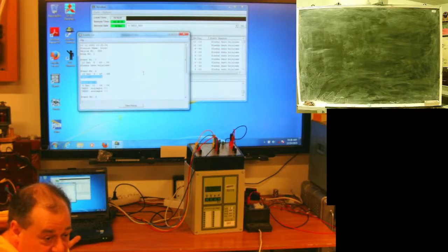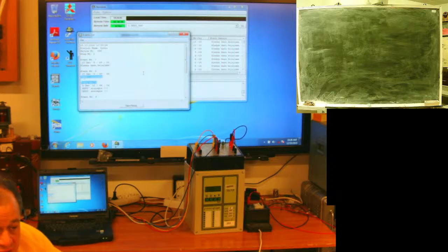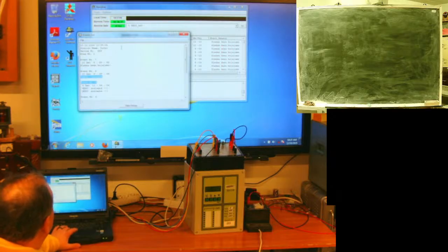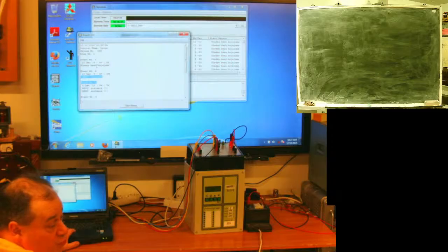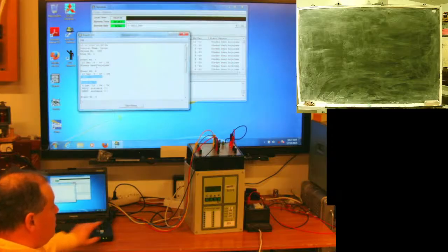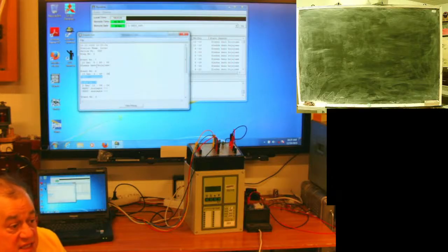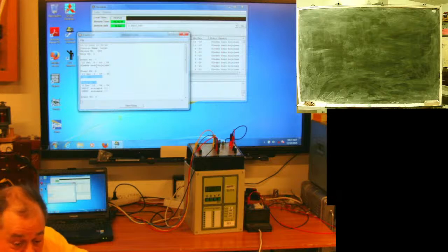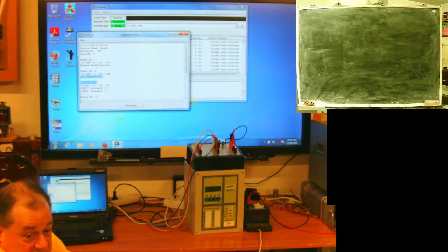What helps me? Events. They are stored in non-volatile memory. Even if the device dies, I can take the memory board, put it in another device and read events. Here, this device gives me 10 events. So here, date, name of the station, device, fault of the switch circuit. The device has monitoring for the state of its switch. If we receive a binary state not allowable, both 1, both 0 and so on, it triggers an event.